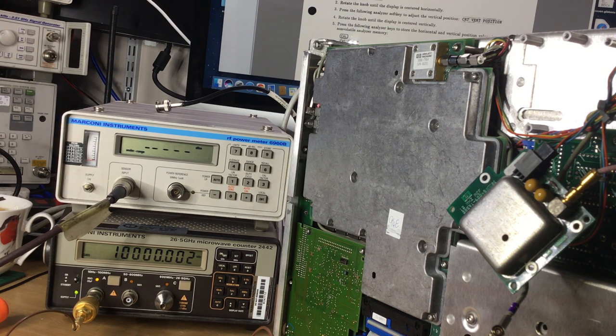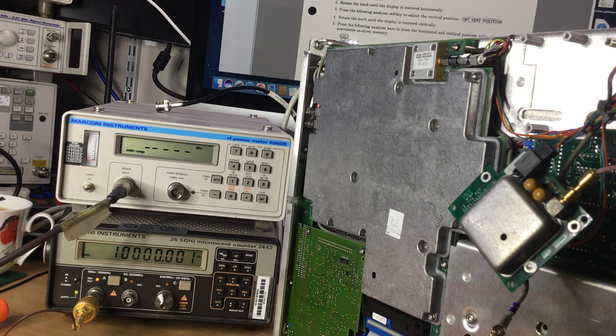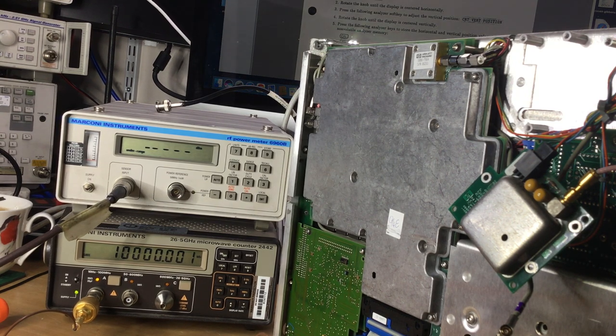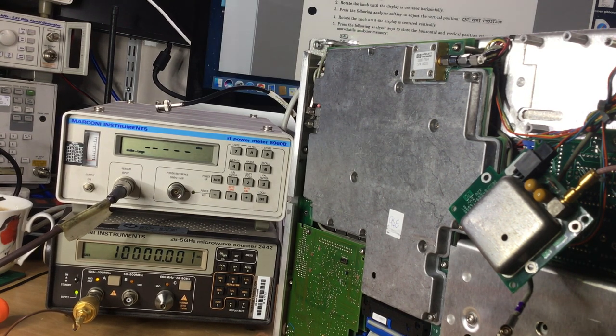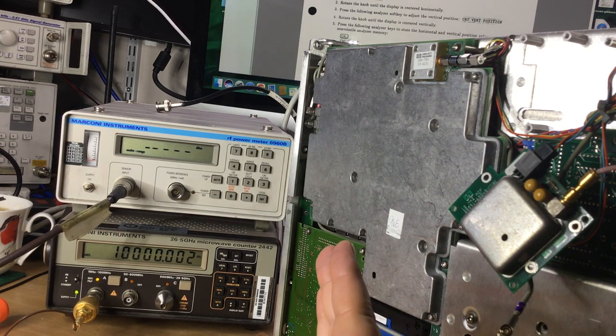there's an oscillator within the instrument, the HP Agilent Spectrum Analyzer, that uses a 10 meg reference from this in order to stabilize the 300 megahertz reference signal. So there'll be sort of a phase lock loop oscillator that's running with a synthesizer that uses a 10 meg reference to keep the 300 megahertz on frequency.